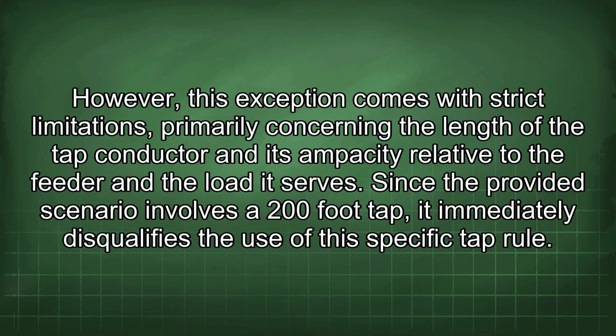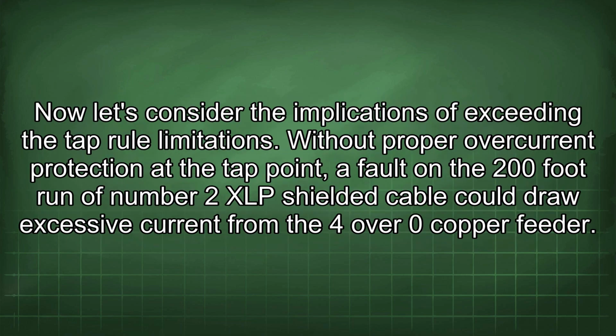However, this exception comes with strict limitations, primarily concerning the length of the tap conductor and its ampacity relative to the feeder and the load it serves. Since the provided scenario involves a 200-foot tap, it immediately disqualifies the use of this specific tap rule. Now let's consider the implications of exceeding the tap rule limitations.